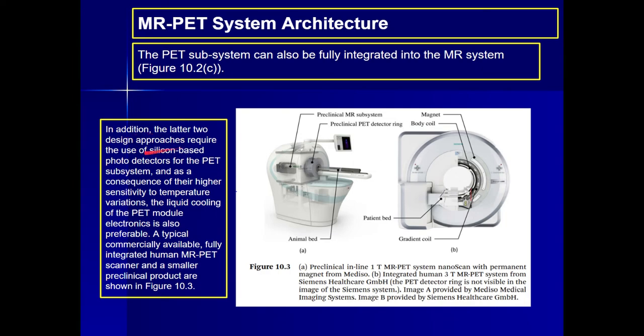In addition, the latter two design approaches require the use of silicon-based photodetectors for the PET, SiPMs, basically avalanche photodiodes. And as a consequence of their higher sensitivity to temperature variations, liquid cooling of the PET module electronics is also required.